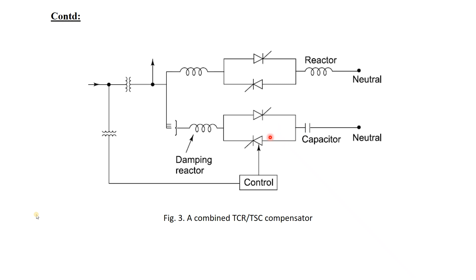Furthermore, full control of both the inductive and capacitive parts of the compensator is obtained. This is a very advantageous feature, permitting optimum performance during large disturbances in the power system. When there is a large disturbance, this combination of TSC and TCR is used. Suppose there is a line fault, a short circuit, an overvoltage fault, or a line-to-line, symmetrical or unsymmetrical fault. In those cases the combination of TSC and TCR provides a very efficient solution to the problem, because the reactors connected in series can consume most of the fault current. They also perform reactive power compensation by consuming excess reactive power, and when required they can also generate reactive power with the help of the thyristor-controlled capacitor setup of the SVC.